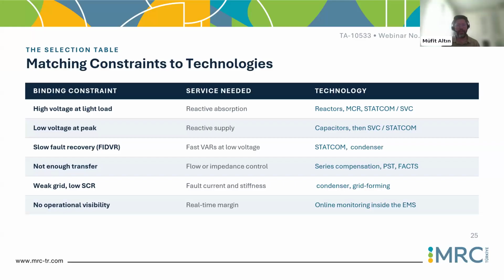Another thing, probably all of you know, is not enough transfer capacity when you have long lines. You need to control the flow and the impedance, of course. So series compensation, phase shift transformers, or flexible AC transmission equipment can again be used. This is a hot topic, the weak grid and low SCRs. I was also working on a couple of projects in Australia.